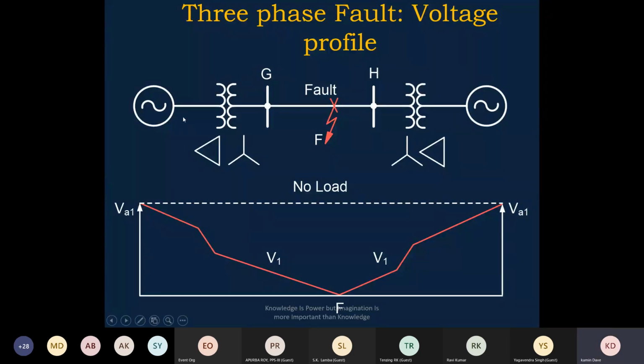Suppose you come to before the transformer, or almost near the transformer on the Y side, then you see the voltage, almost you get 60% voltage. So this is how you look at it here. The V1 profile is getting changed. When you go away from the fault, the V1 is getting increased.